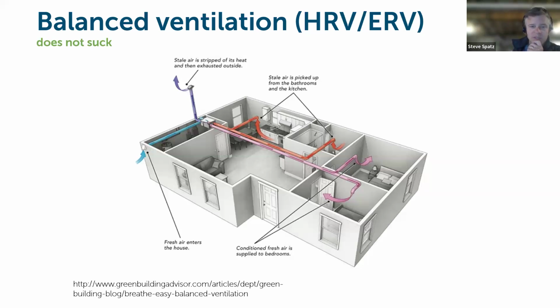But a key component to a successful outcome in this is that the HRV or ERV that you're choosing to use has the capacity to move X number of CFM and recover X percent of heat energy from the exhaust stream of air to be put into the incoming stream of air. And another detail to be paying attention to here for our climate is that it has a good defrost strategy. There are definitely differences in equipment out there on the market. What you definitely want to be putting in our climate is an ERV or an HRV that can still operate when it's 10 degrees outside, and it will not be shutting off or recirculating because the cold air coming in is freezing up the core. That's when we really need the ventilation the most, during the cold winter months.